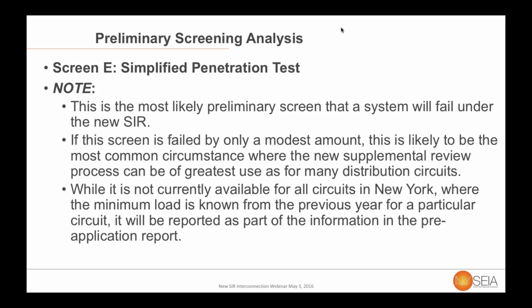So supplemental review, as Melissa mentioned, will not be useful for all systems. You certainly wouldn't imagine sending all of your systems through it, but there is likely to be a sweet spot of systems in that 200 to 1 megawatt range, where on certain types of distribution lines with certain load profiles, they really will be a huge help to us.